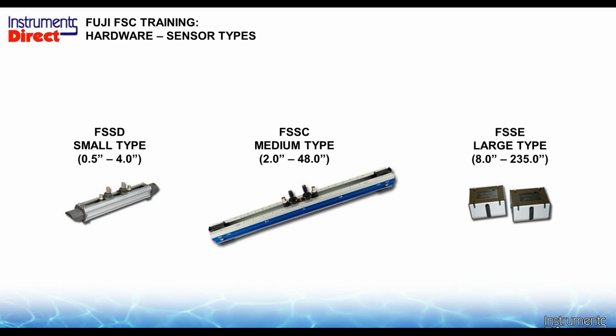The breakdown of the transducers, and this is really what separates the Fujis from the bargain brands, is you need to have a device with multiple frequencies, and that is a sign of the intelligence and the signal processing of the device. The FSSD is an adjustable small pipe transducer that is 2 megahertz, and you can use that, as you can see, from 1/2 to 4 inches. The FSSC is the workhorse. It works from 2 to 48 inches, and it has some special features I'll show you in a minute. So it can do all the medium-size or middle-range applications. And if you have some giant penstock applications, you want to go a couple hundred inches, we have a 1/2 megahertz transducer on the FSSE.